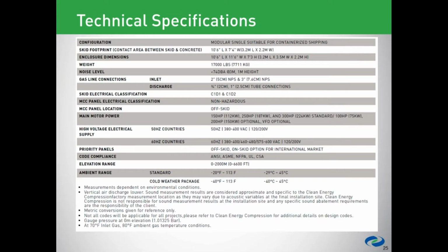And in general, when we're sending out the specification sheets showing the predicted performance of our compressors, when they go to the test bay, we are often 5 to 10% higher on the flow rate compared to what we predicted, and several 2 to 5% lower on the power consumption that's been predicted. So yes, definitely some improvements made there. Excellent. And for our international clients, speaking of power and power consumption and power costs, I know in BC we're not that worried about electricity costs, but we do have a gas engine drive unit called the unplugged CNG, and those are used in applications in Africa, Indonesia, Egypt, where either power is intermittent or power cost is prohibitive.